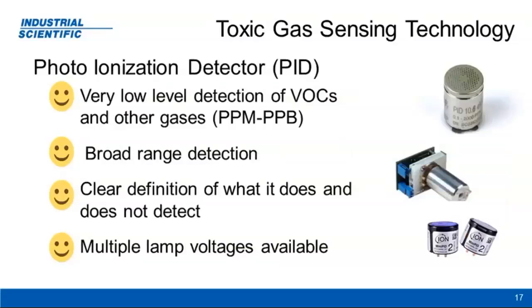A lot of toxic gas detection, particularly for toxic levels of hydrocarbons, has gone to photoionization detection, or the PID. The benefit of a PID is that you get very low level detection of VOCs and other gases, in some cases down to ppb levels, over a very broad range of detection. One advantage the PID has is that there's a very clear line of what you can and cannot detect based on the lamp voltage. If your ionization potential is above 10.6, you're not going to detect that gas with a 10.6 lamp. As simple as that.